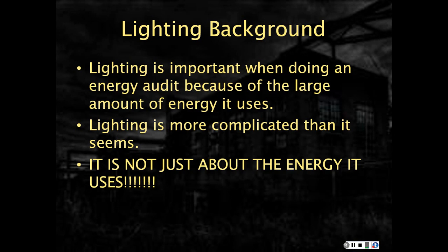In essence, they were trying to go from a 40-watt lamp down to 34-watt, basically save 6 watts per lamp, but thousands of lamps. It seemed like an innocent thing to do, but it turned out the lighting in this situation was a lot more complicated usage than simply about the energy that it was using. So be really careful. Typically, if I have complex lighting issues, I get a lighting expert in because it can be tricky.